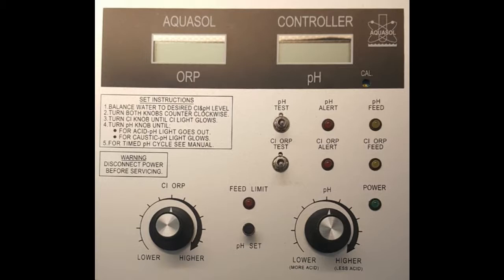What I like to tell guys to do is, first of all, test your pH first. Once you test, you do an internal calibration first, and then external lastly on the face panel, because that one just calibrates the digital readout. So you're basically matching that to your test kit reading. Right. So say for instance you calibrate internally on VR17. Once you have that set point, next you would calibrate on the face panel so that they can tweak it in to match your test kit reading.